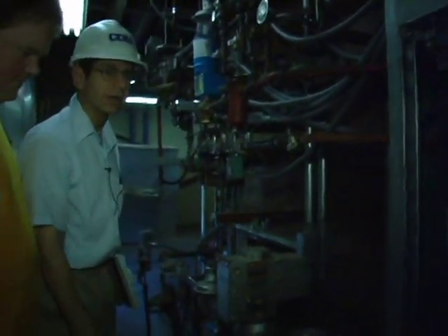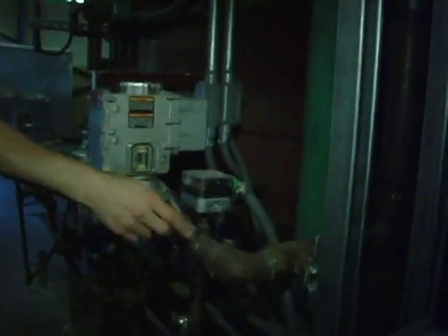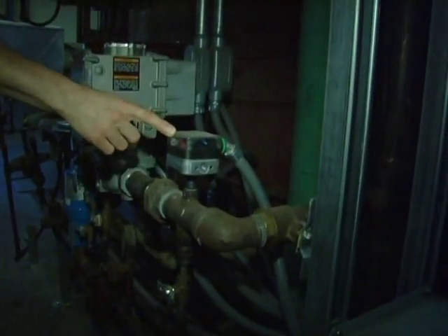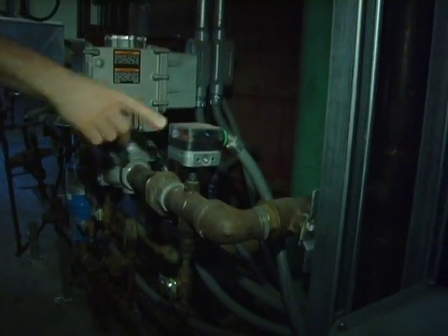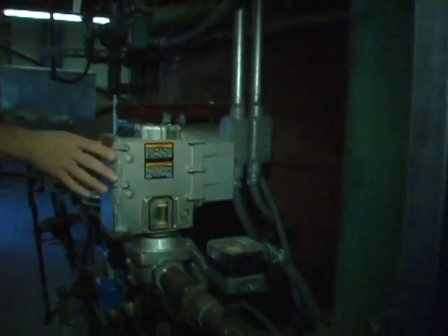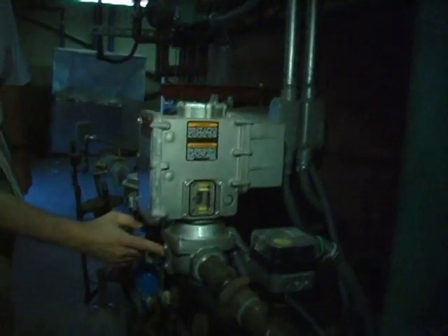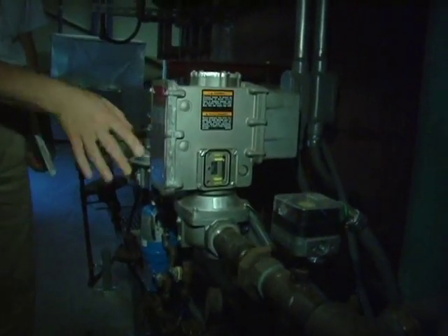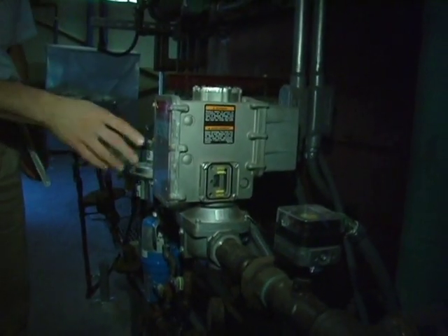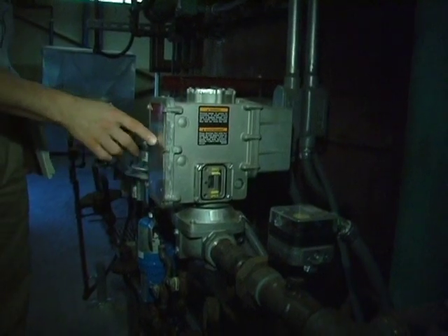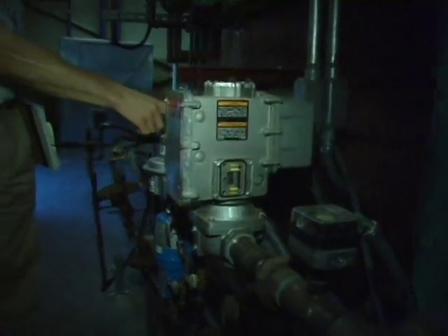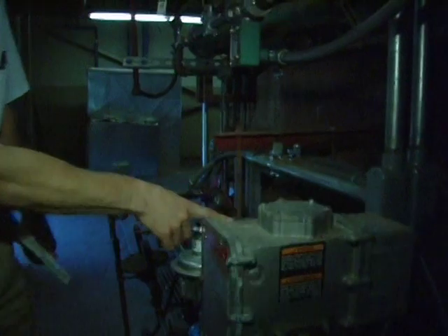So here we have a redone burner train. Okay? This is your gas line coming in. Pressure sensor here. This would be a high pressure sensor. This is your automatic shutoff valve. A valve down here with an electric actuator, kind of like a solenoid actually. Okay? And then you go to a low pressure sensor here.